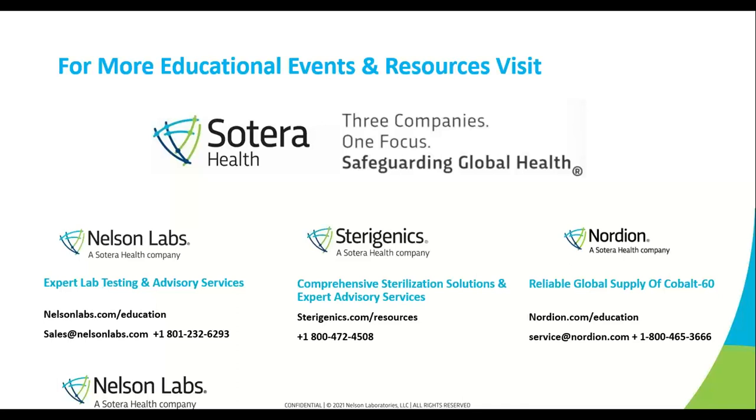Question: How often do you perform an integrity test? An integrity test could be performed right after the filter is manufactured, just ensuring that the lot manufactured meets the integrity test specifications. We also like to run an integrity test after a filter has gone through the sterilization cycle, to make sure that there were no adverse effects from being sterilized — this is pre-use, post-sterilization integrity testing. And then there will always be an integrity test performed after the product has been filtered, to make sure that the filter stayed intact throughout filtration.